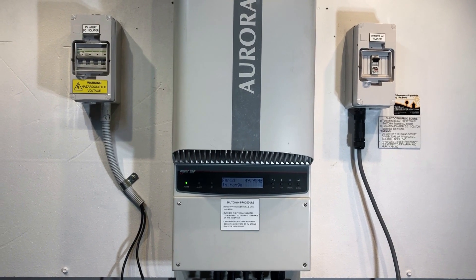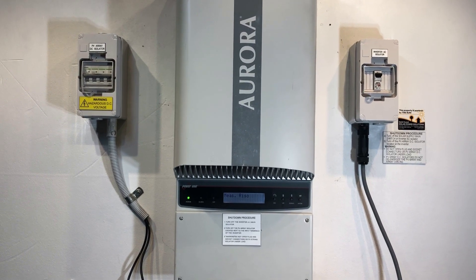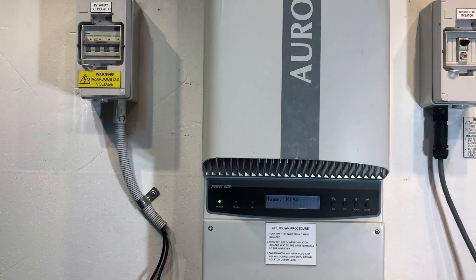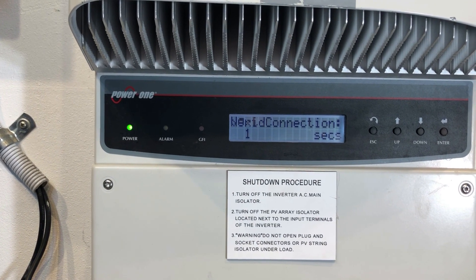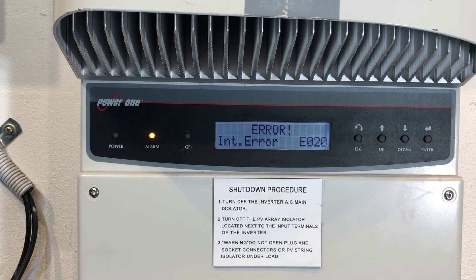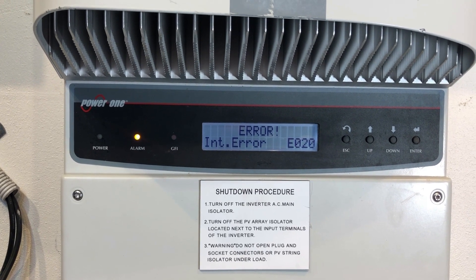Hi, Simon here from Goldco Solar Power Solutions. Today we have a Power One Aurora Inverter — or it could be an ABB Aurora Inverter — and if we have a look at the screen of this one, we can see it's just come up with the orange alarm lights on and error: internal error E020.